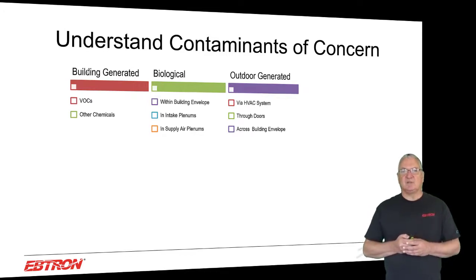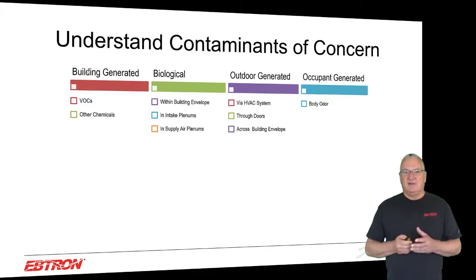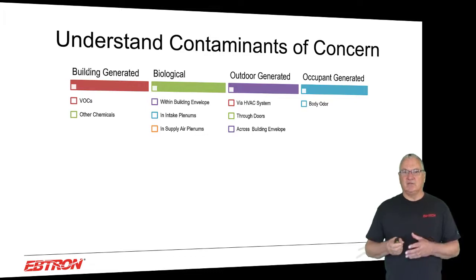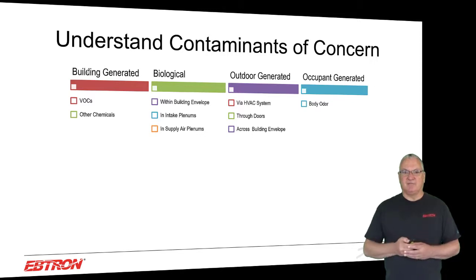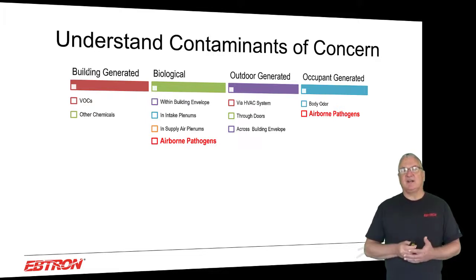Entry through doors and across the building envelope is more pressure-related — bringing in untreated, unfiltered outdoor air because the building is negative. And then finally we have occupant-generated contaminants, which too many people concern themselves with exclusively. This is primarily body odor or human bio-effluents. With COVID-19, we now also have airborne pathogens, whether you consider them biological or occupant-generated — it really doesn't matter.